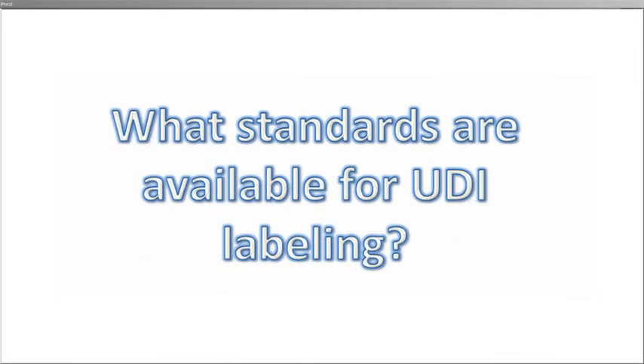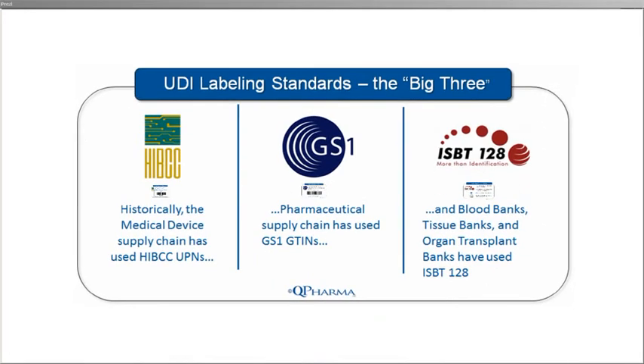Tom, what standards are available for UDI labeling? There are three main labeling standards that can be used for the device identifier component of UDIs. In no particular order they are: HIBCC UPNs, or universal part numbers, which have been historically used in medical device supply chains; GS1 GTINs, or global trade item numbers, which have been widely used in pharmaceutical supply chains but have been expanding into medical devices; and ISBT 128 codes, which are commonly used in the blood and blood product sector as well as in organ transplant labeling. These traditional alignments are evolving rapidly, and each standard has positives and negatives that you need to carefully consider for your organization.